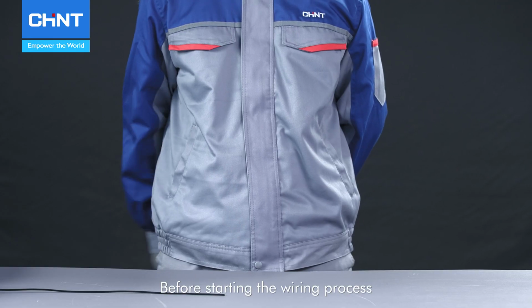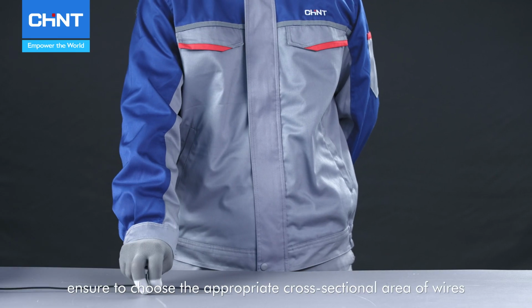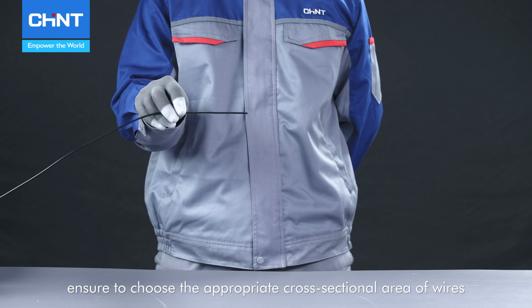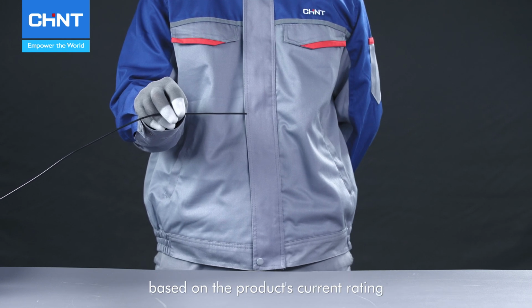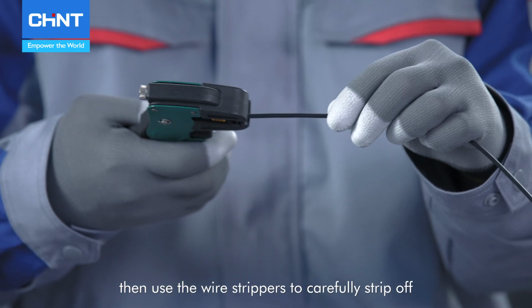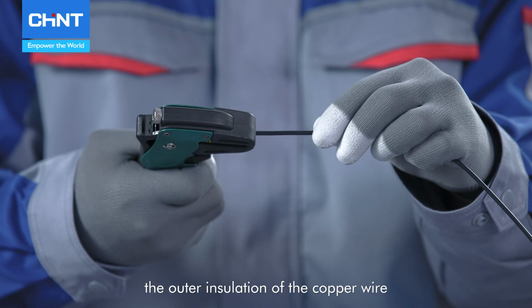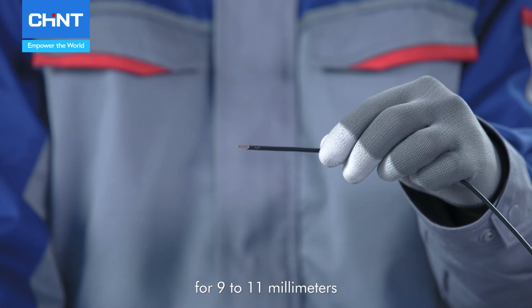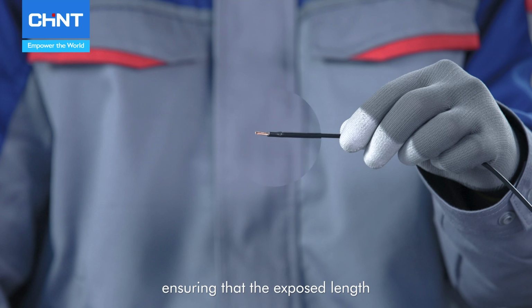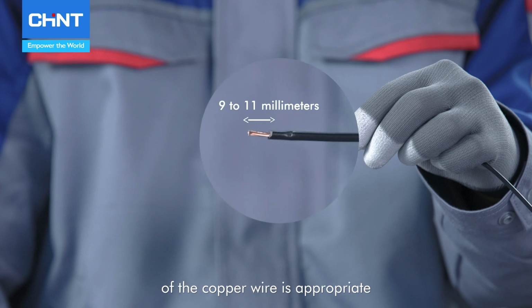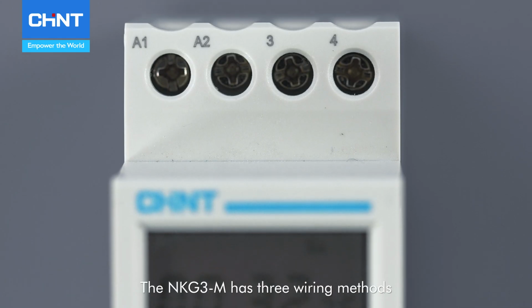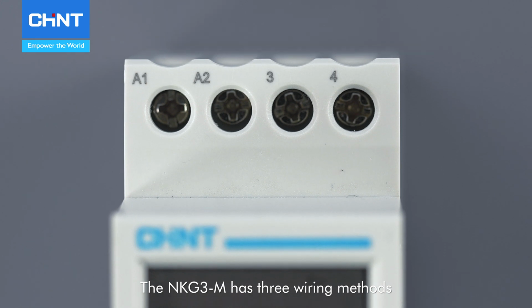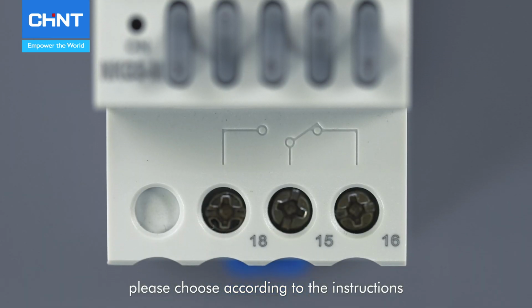Before starting the wiring process, ensure to choose the appropriate cross-sectional area of wires based on the product's current rating. Then use the wire strippers to carefully strip off the outer insulation of the copper wire for 9 to 11 mm, ensuring that the exposed length of the copper wire is appropriate. The NKG3-M has 3 wiring methods. Please choose according to the instructions.